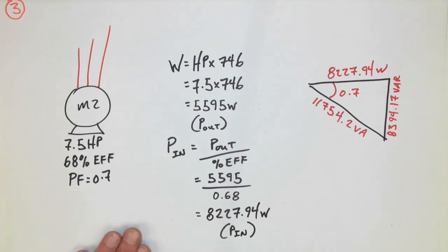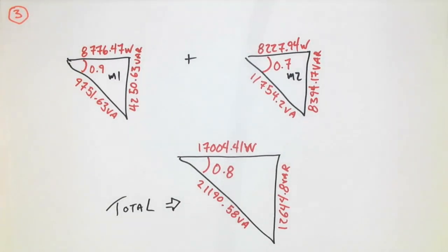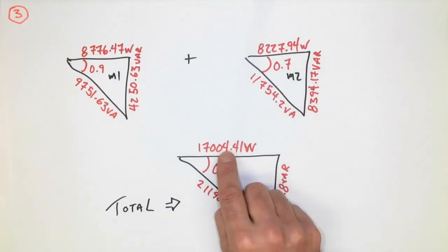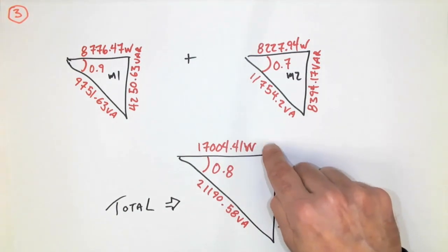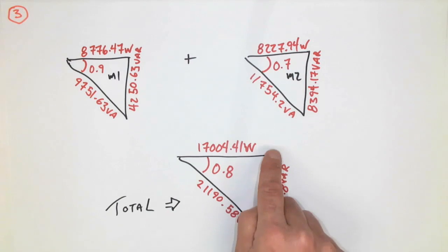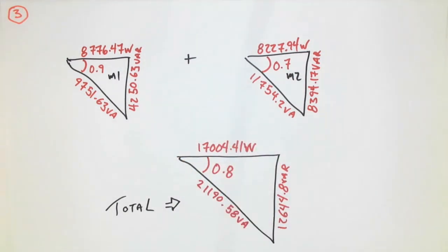Finally, the last step is to take these two power triangles and add the vertical and horizontal components together. I've added the two watt input values to get just over 17,000 watts, and the VAR values add to 12,644. Using the horizontal and vertical with Pythagoras, I get the total VA. To calculate the power factor, I take the horizontal divided by the hypotenuse, which gives me 0.8.